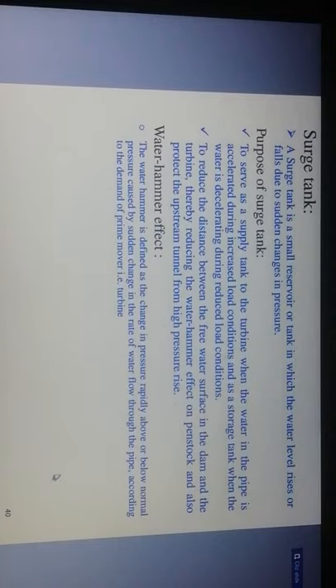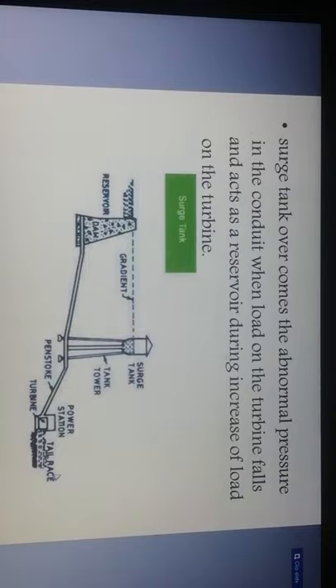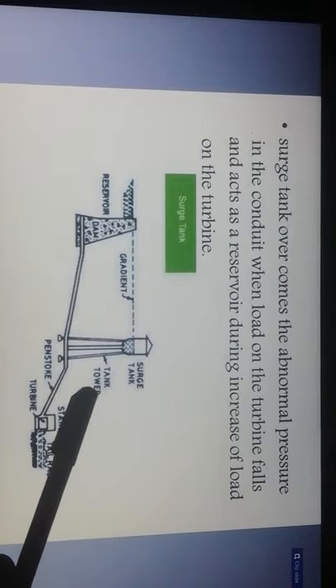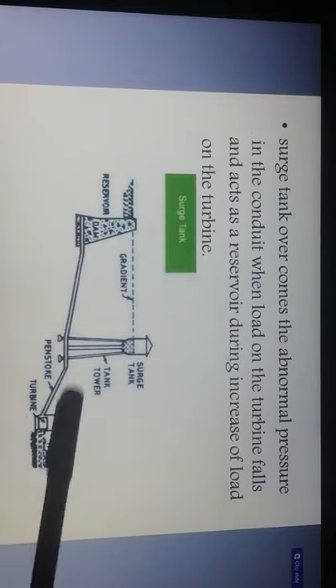The water hammer effect is defined as rapid changes in pressure above or below normal pressure caused by sudden changes in the rate of water flow through the pipe according to the demand of the prime mover or turbine. The surge tank overcomes abnormal pressure in the conduit. When the load on the turbine falls, it acts as a reservoir; during increase of load on the turbine it again acts as a reservoir. The surge tank is connected to the penstock leading to the power station and turbine, with the remaining water flowing to the tailrace.